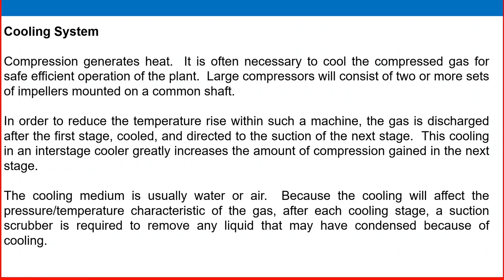The third auxiliary system is the cooling system. Compression generates heat, and it is often necessary to cool the compressed gas for safe, efficient plant operation. Large compressors consist of two or more stages mounted on a common shaft. To reduce temperature rise, gas is discharged after the first stage, cooled in an inter-stage cooler, and then directed to the suction of the next stage. This greatly increases the amount of compression gained in the next stage. The cooling medium is usually water or air.